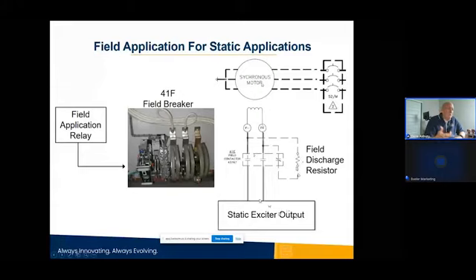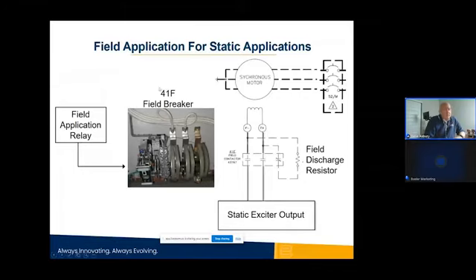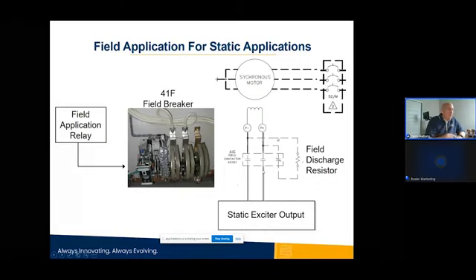So once the synchronous motor starts the process of coming up to speed, the field application relay is sensing right across the discharge resistor, looking at the slip between the RMF and the rotation speed of the rotor. And as that approaches synchronous speed, at that precise moment, we're going to apply excitation and then remove that field discharge resistor from the circuit. And at that point, that's when the induction motor becomes synchronous.